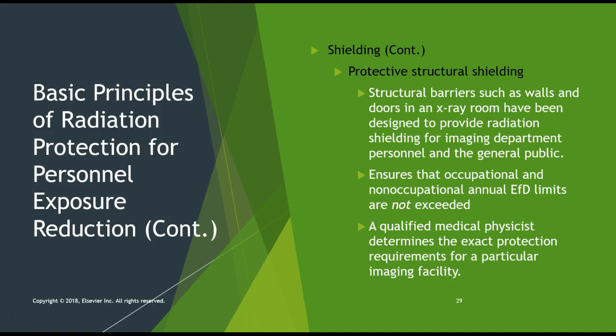Okay, shielding continued. Protective structural shielding. This is where we get into structural barriers, such as your walls and your doors in an X-ray room. They have all been designed to provide radiation shielding for the department and the general public. It ensures that occupational and non-occupational effective dose limits are not exceeded. And this is done by calculations that a qualified medical physicist determines.